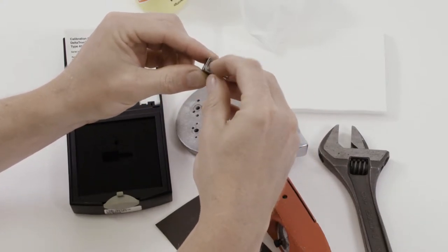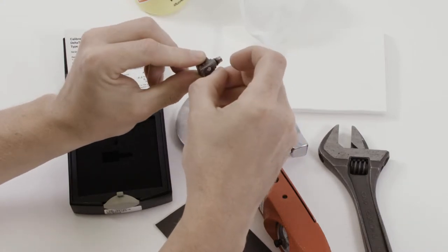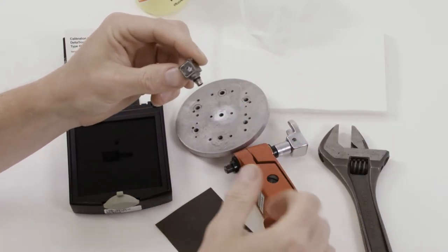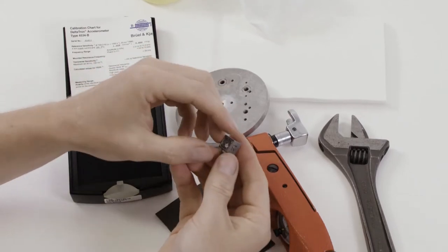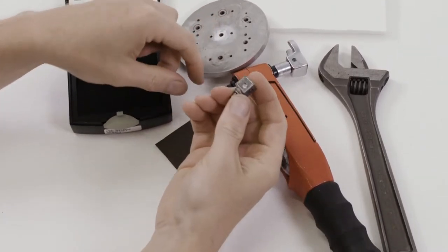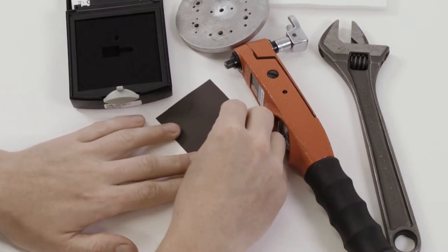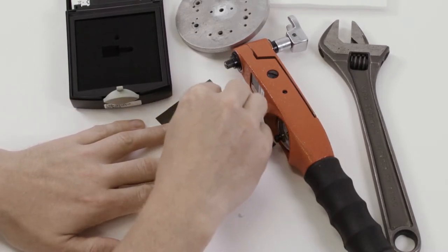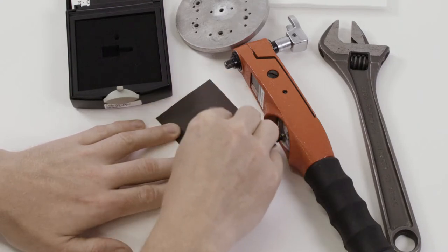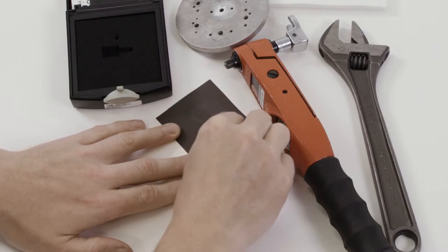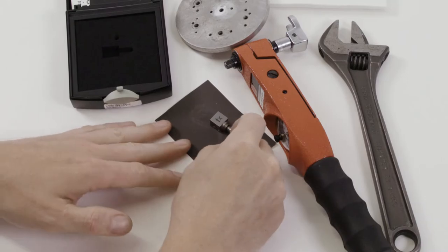In order to remove the residue of glues, mechanical removal first of all should be done. Finally, after removing what can be removed mechanically from the surface, again use, for example, the fine graded sandpaper and figure eight circles to prepare again the surface for remounting the accelerometer.